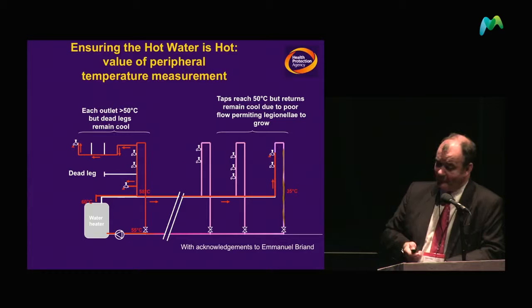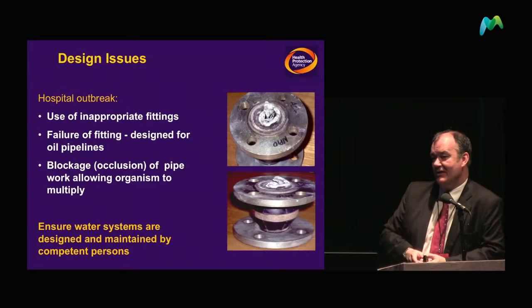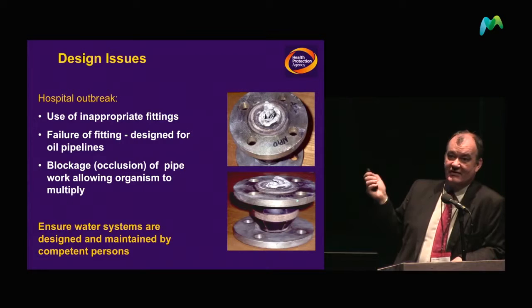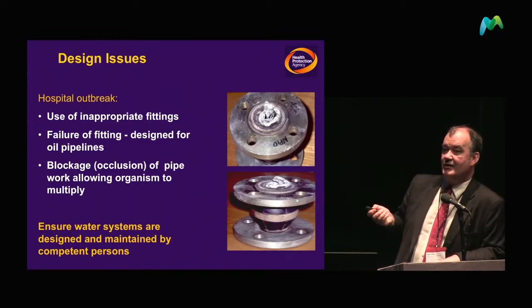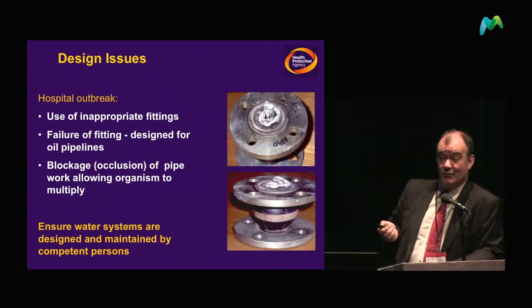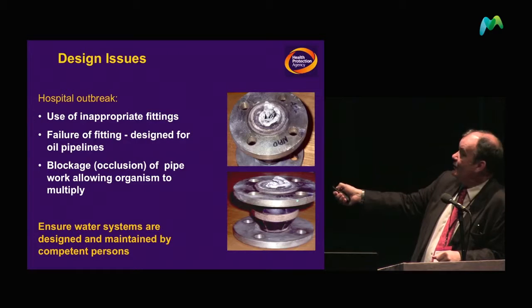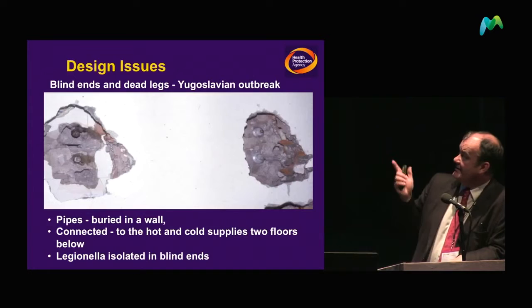Identifying Legionella in the water system is only the start. In this hospital outbreak, one of the components used in the hospital system should actually have been used in a pipeline, not in a water system. You are dependent to a large degree on contractors knowing that they've done it properly. Scale resulted in almost an occlusion of the water, so what you ended up with was stagnation and a potential source of Legionella.